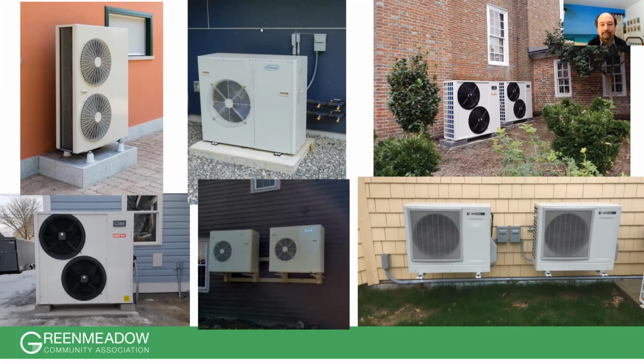If we take the Chiltrex, for example, it needs about 14 inches behind it and 40 inches in front so air can come in through the back and go out through the front. It needs that air movement to extract energy for heating or cooling. The sound on these high-performing, modulating heat pumps is really just the air, the compressors are very quiet. So placement could be on a roof or on a deck.